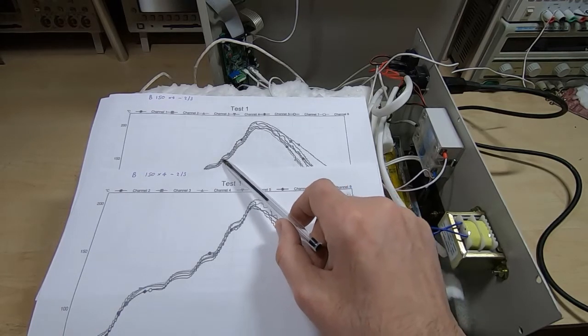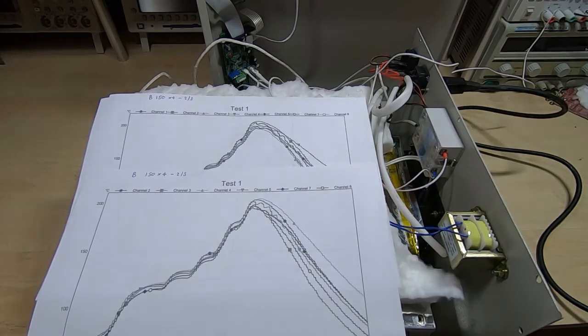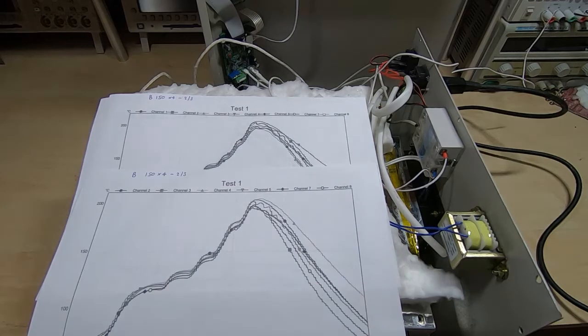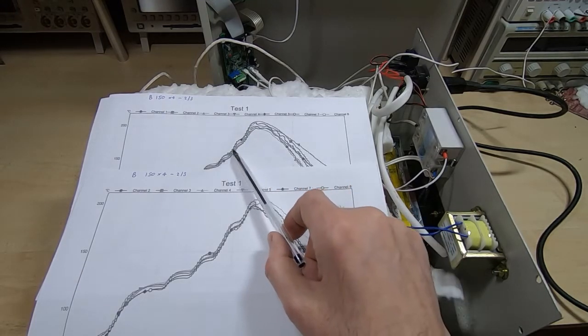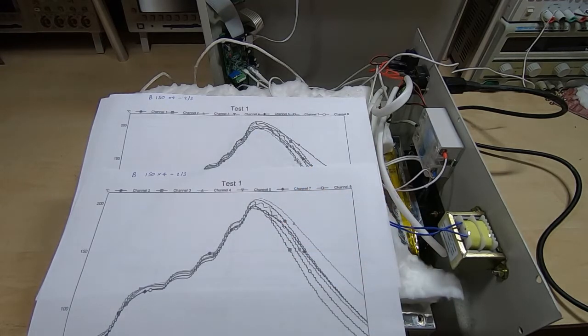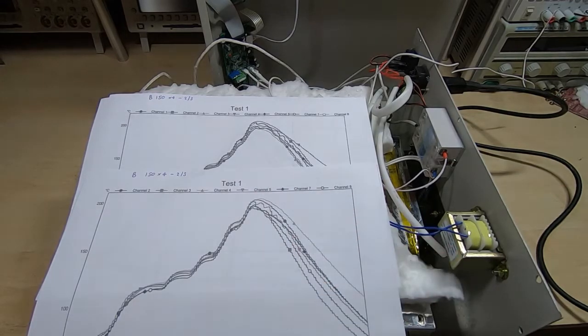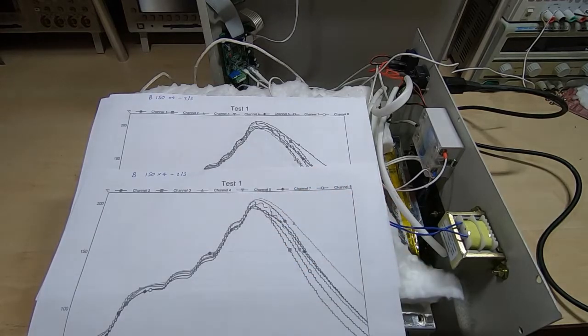So although you see these steps that's not truly indicative of necessarily when the particular reading was taken. And you need to take that into account what we're aiming for here is effectively a single line. When we can guarantee that the entire spread is within one or two degrees. And in order to do that we need to have very good relationships between the different probes that we're using. In other words we need to look at very homogenous readings across the entire set of probes we're using. Both in the time domain and of course in the calibration and temperature. So that's something that you need to take into account.